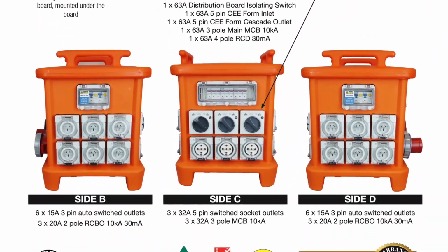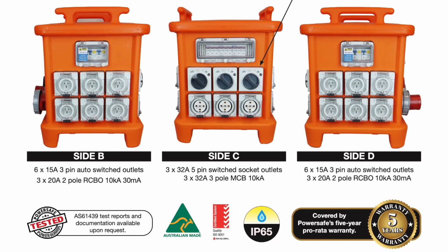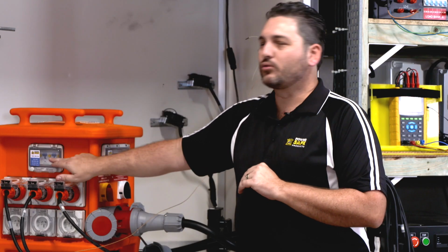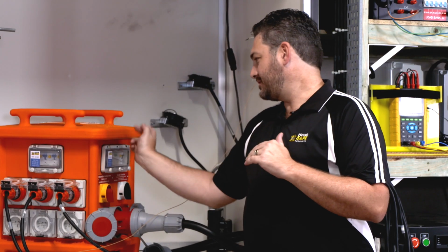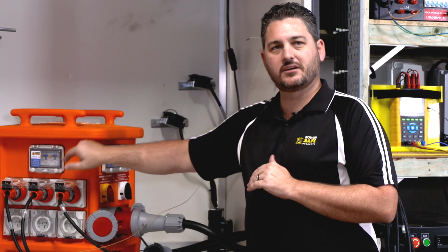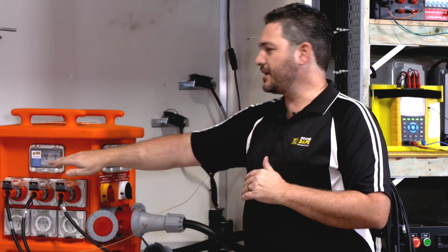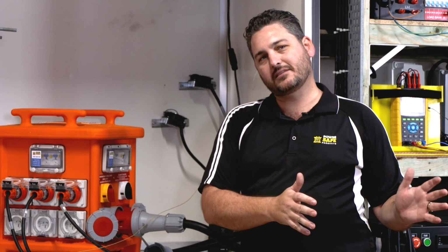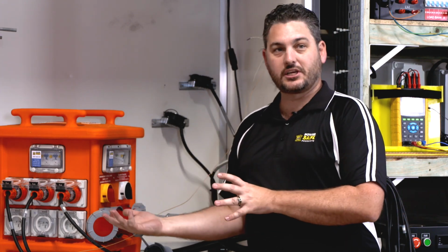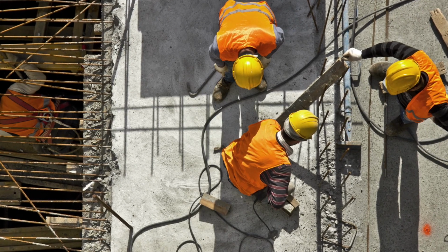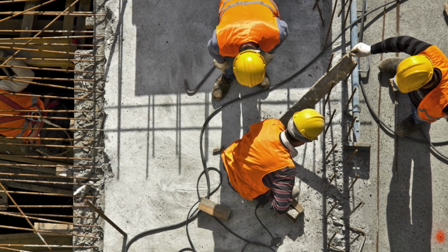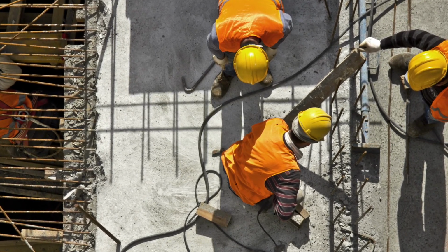All the RCDs and componentry we use is at the top of the market. These are all rated at 60 degrees for the RCDs, 75 for the RCBOs. A lot of your domestic products are only rated at 40 degrees. So if there's a manufacturer out there and they're using domestic switchgear in there, by the time you put it out in the sun, she's cooked. You can't run any power through it, you're going to overheat those components.